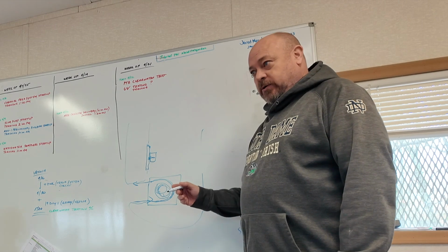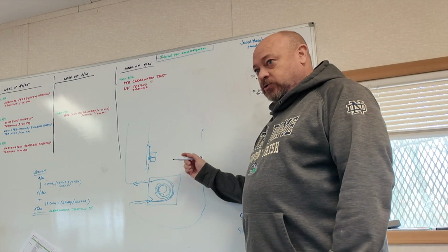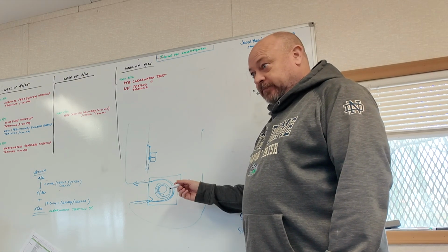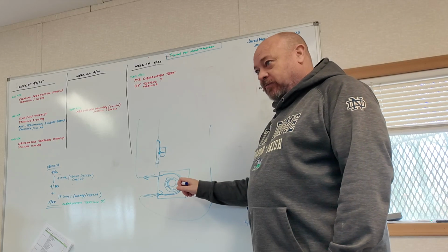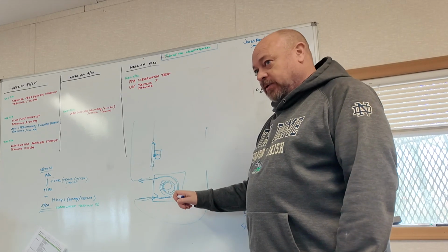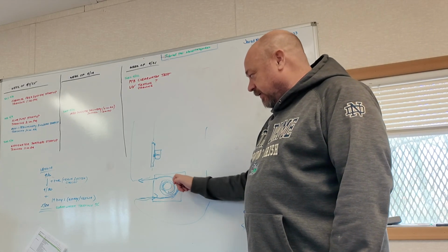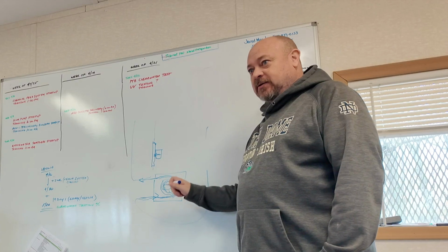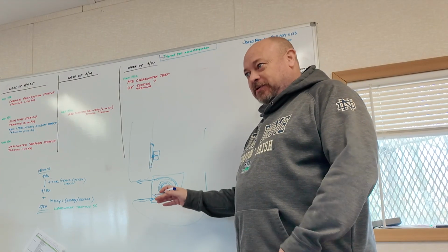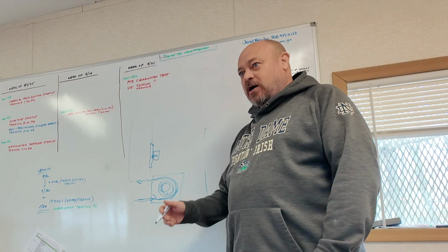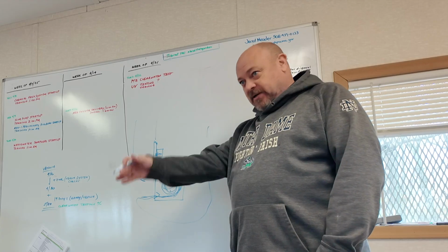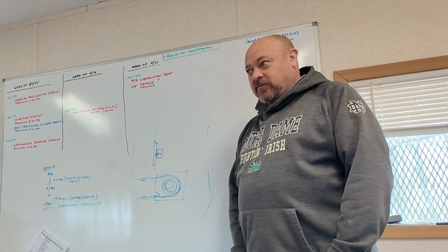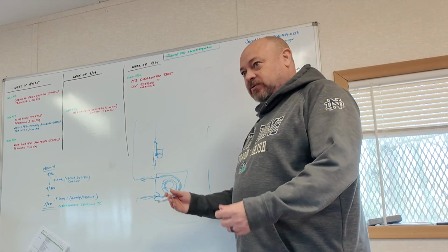The roller is 0 to 125 revolutions per minute. If you run it at 125 revolutions per minute, you're going to be calling me every 3 months or so to be getting new tubes. The pump is not designed to run continuously at max speed. It'd be like getting in your car, hitting the gas and doing 180 miles an hour just 24/7, right? Eventually you're going to crash into something or the car's going to break down.